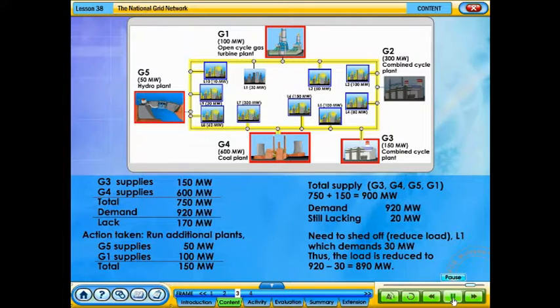By running the generating plants G1 and G5 to supply power to the grid, and at the same time shedding off L1, the total generating capacity supplied to the grid will increase to 900 megawatts, which will meet the demand of about 890 megawatts, and yet with some spare capacity to cater for any small fluctuations in load demand. The grid system is secured, and the consumers, except those at load center L1, will not experience any interruption of power supply.